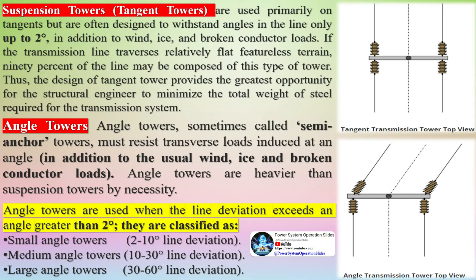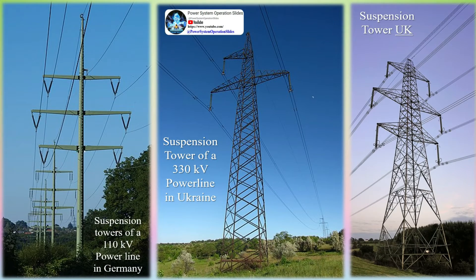Tangent towers are used primarily on tangents but are often designed to withstand angles in the line up to only 2 degrees, in addition to wind, ice, and broken conductor loads. If the transmission line traverses relatively flat, featureless terrain, 90% of the line may be composed of this type of tower. Thus, the design of the tangent tower provides the greatest opportunity for the structural engineer to minimize the total weight of steel required for the transmission system.